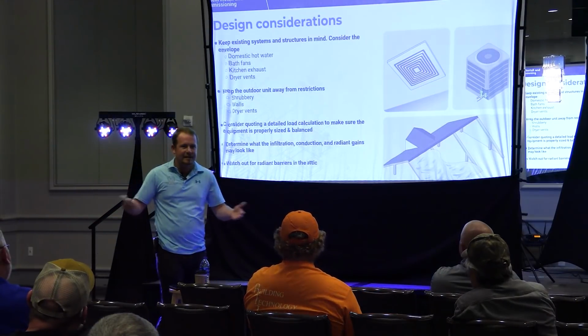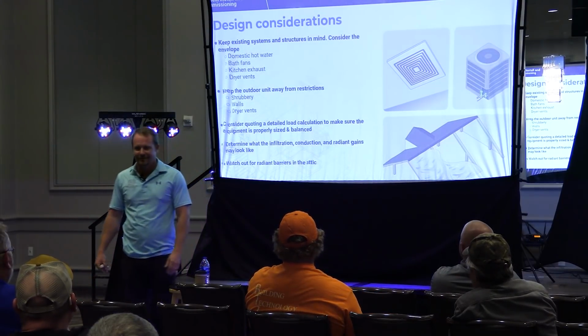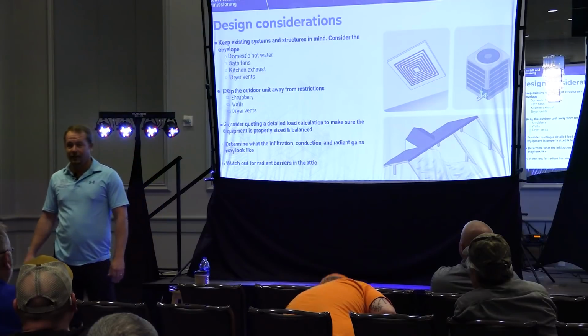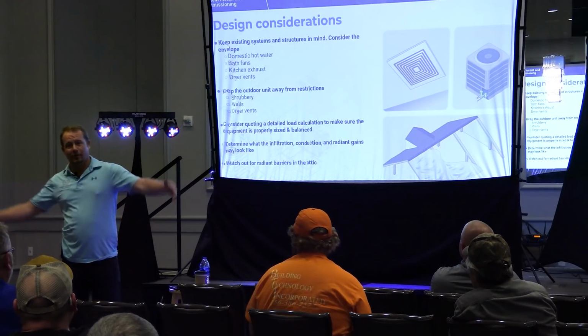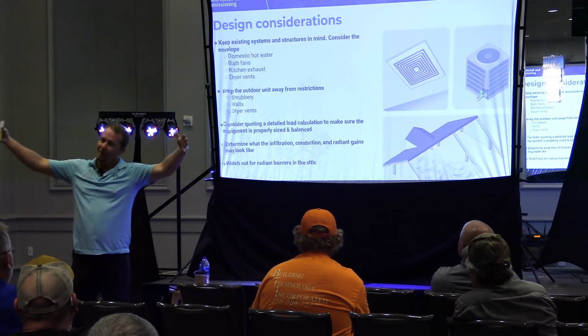There's no compensating factor in Manual J for combustion air going into an attic. You just think, hey, if a 12 by 12 is good, a 24 by 18 is even better, right? Just give it more, we want to be safe.